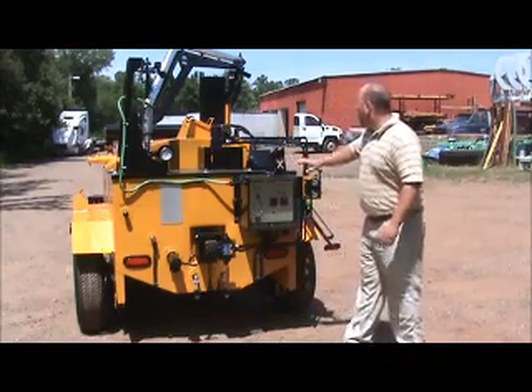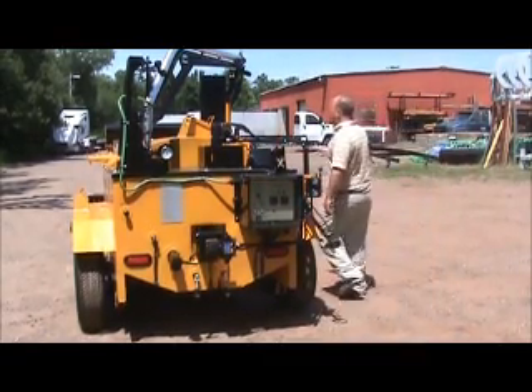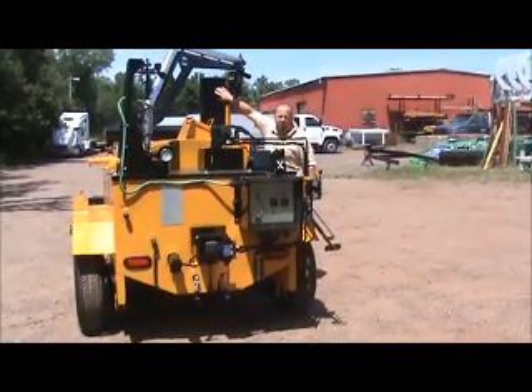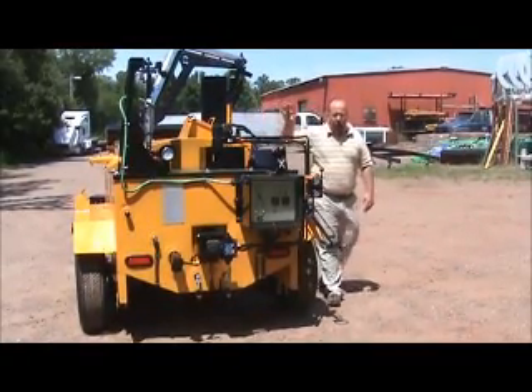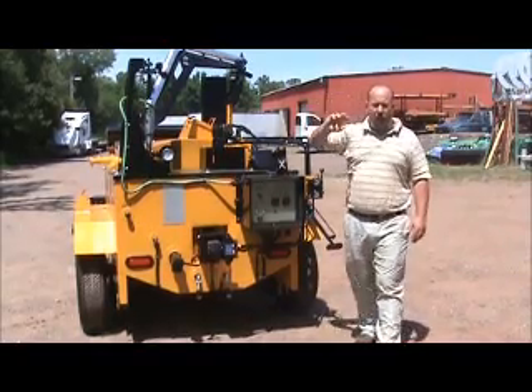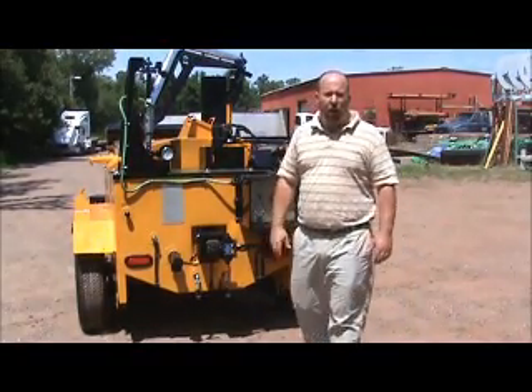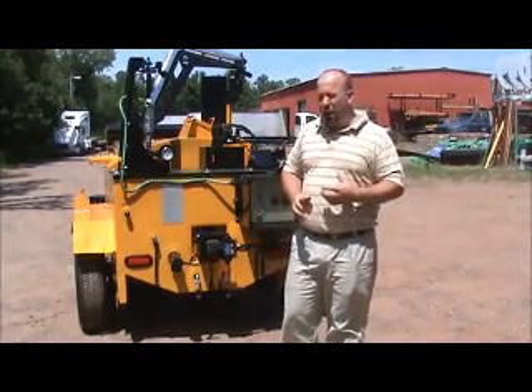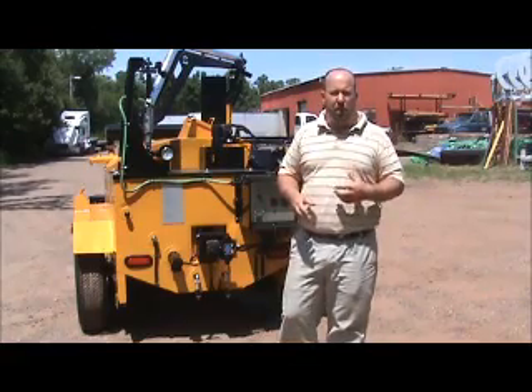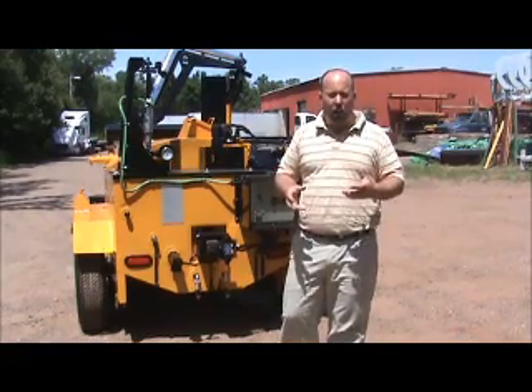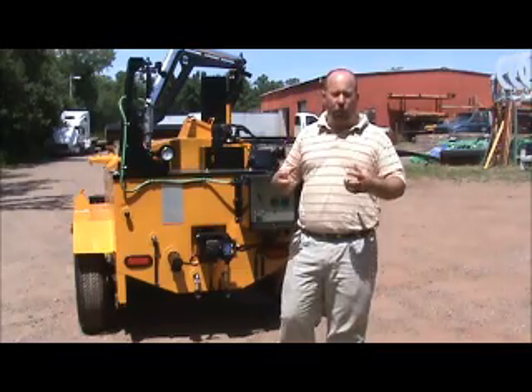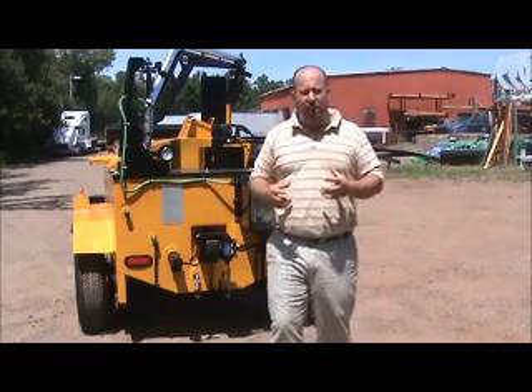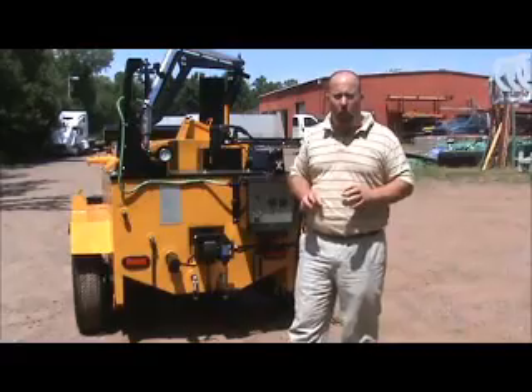The diesel burner, you'll be able to see when it fires. It's very hard to see. You shouldn't have any smoke coming out of the stack. You'll have to look for the heat coming out of the stack, and you'll be able to hear the burner fire. It'll hiss. If for some reason there's a burner malfunction, it's going to try to light. If it doesn't light the first time, it's going to try for reignition. If it doesn't reignite the second time, it's going to go into a lockout mode.